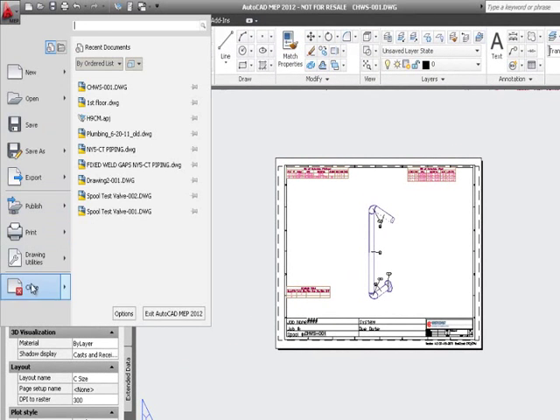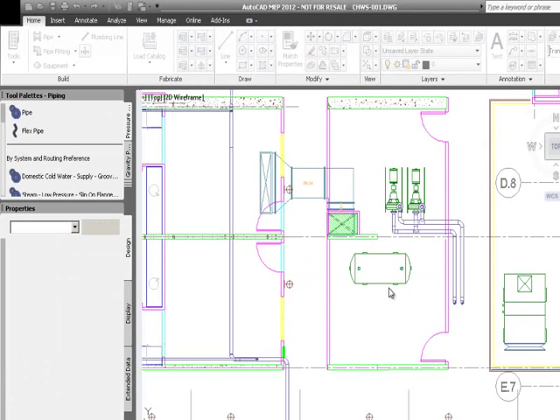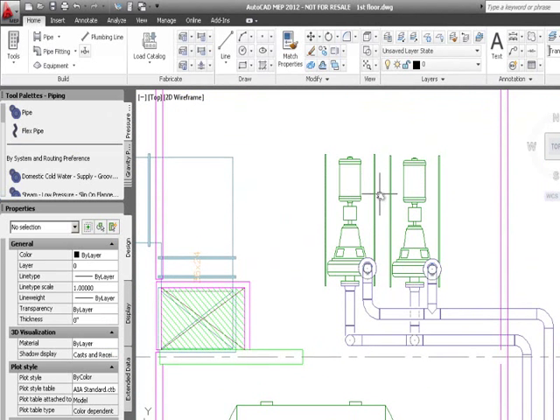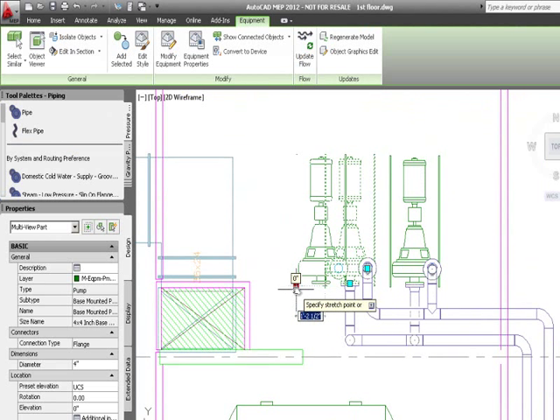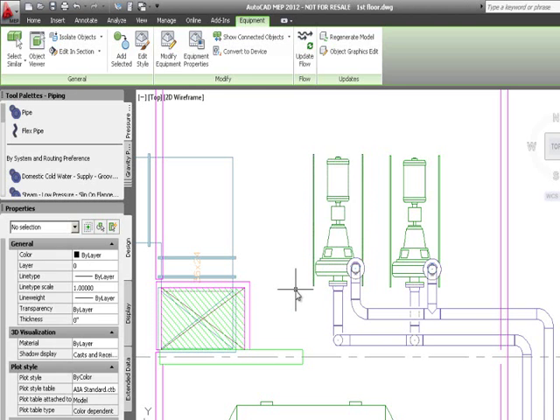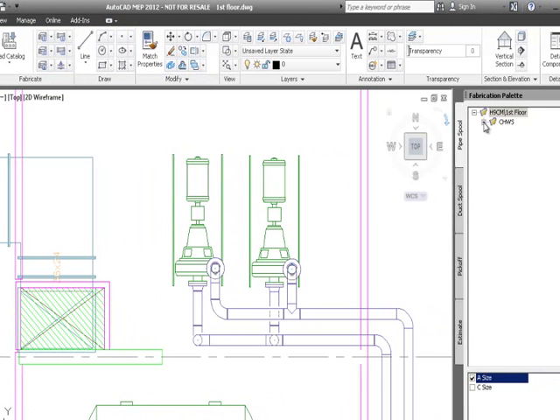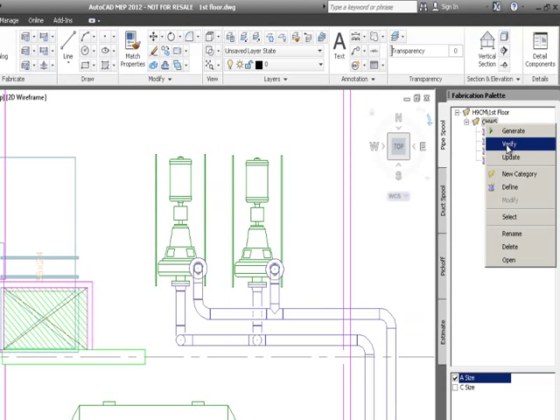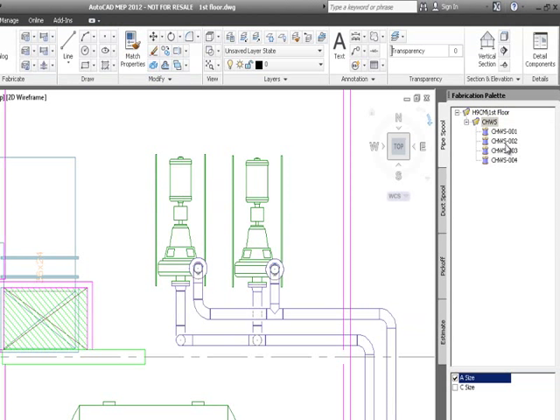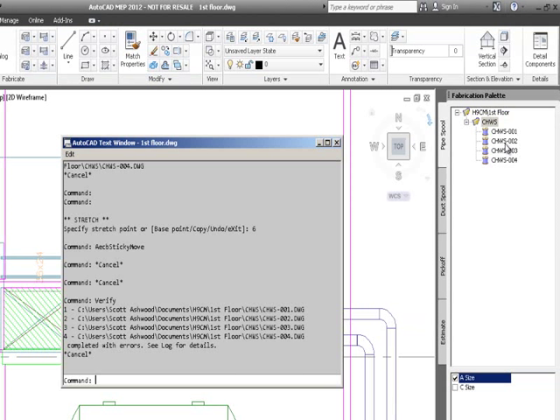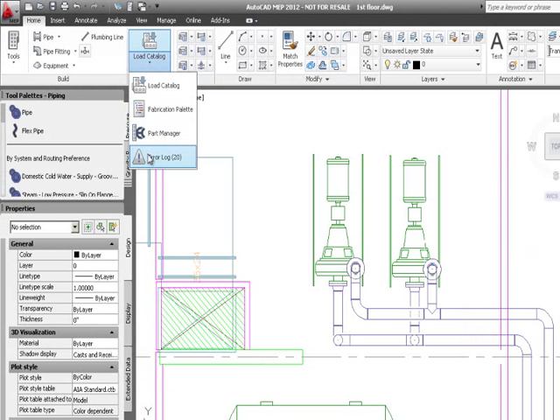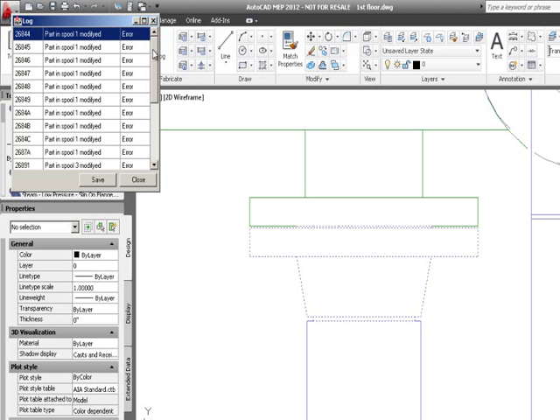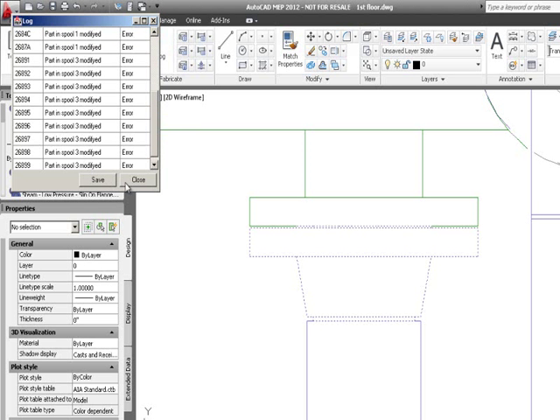I close the spool drawing and go back into the model to make a change — someone called and said the pump has been moved. I grab the grip and move the pump six inches to the left; everything stretches accordingly. Coming back to my spools, I click and run a verify on those spools. The verify completes but the log shows errors — the error log tells me parts were modified in spool number one and spool number three.